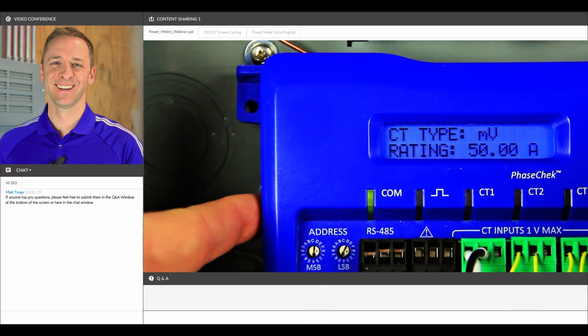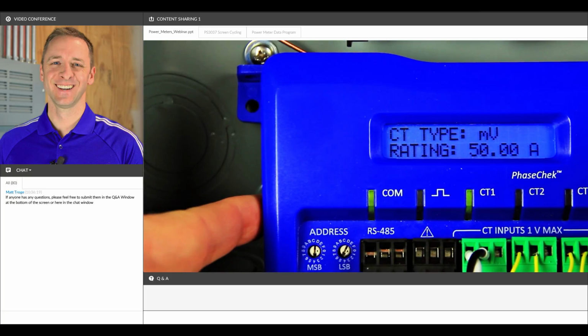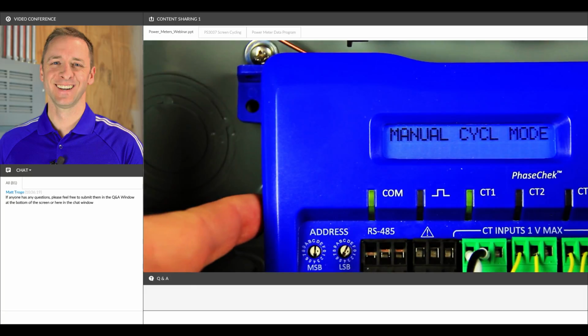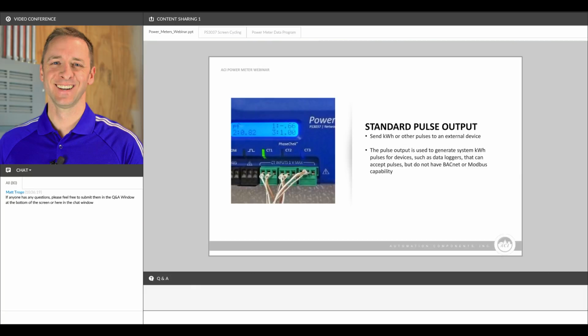And this is an easy way to view in real time what's being measured by the PS3037. It also has a standard pulse output that can be used to send a kilowatt-hour signal to a non-BACnet or Modbus device, like a data logger, something that can accept a pulse. This device has 2 pulse outputs that can communicate to that.